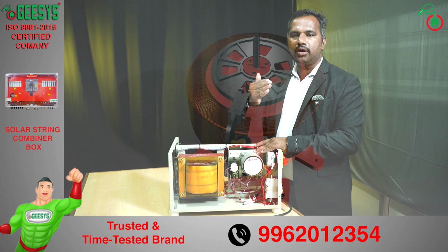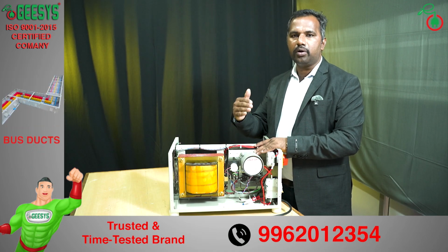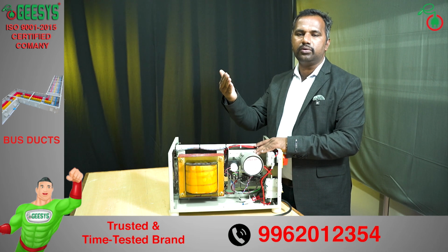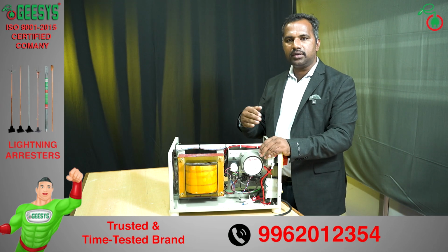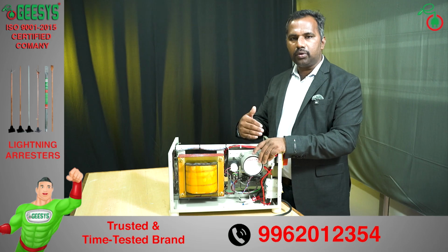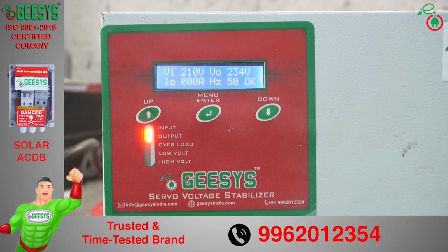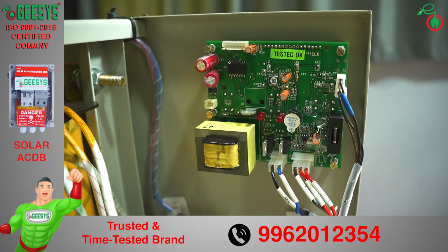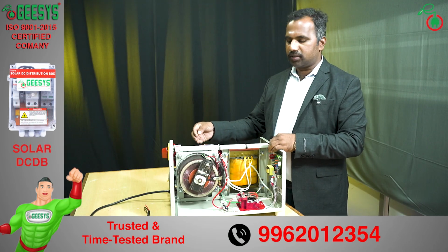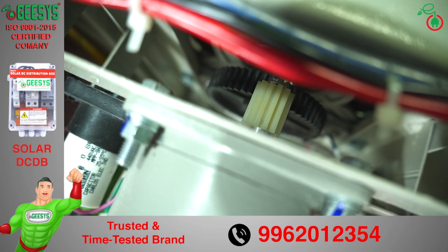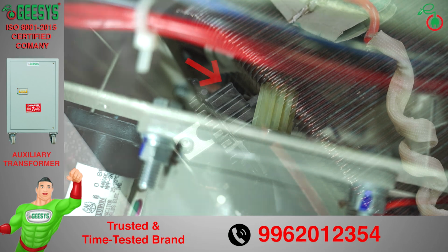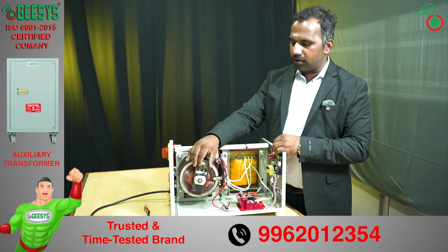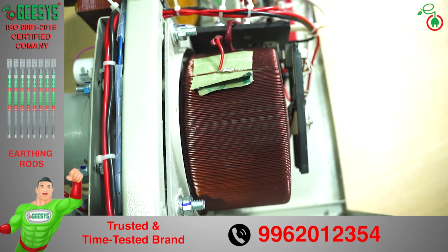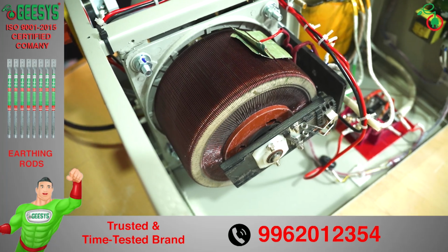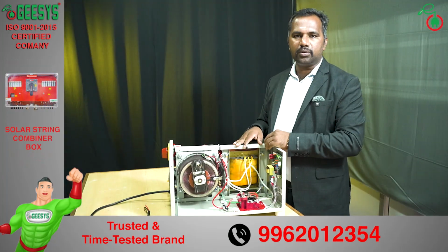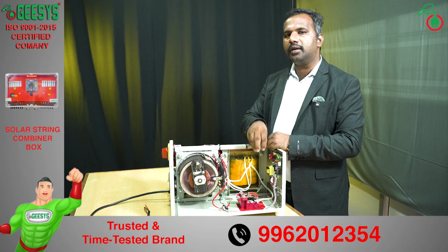So in case you have a low voltage, it will move forward to boost the voltage to 230 volt, and in case of high voltage it will move in the reverse direction to buck the voltage to 230. So that direction of movement is controlled by the motherboard. This servo motor is connected to a variac through a gear mechanism. This variac has a carbon brush moving over it to adjust the input voltage and give a continuous constant voltage at the output. So this complete servo stabilizer is connected through a relay.